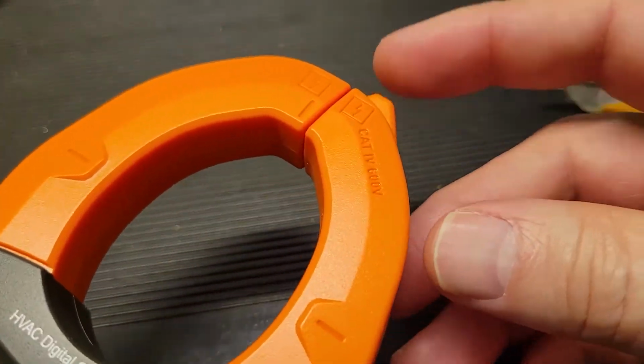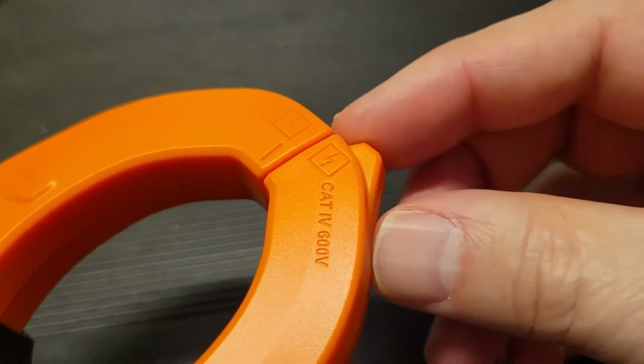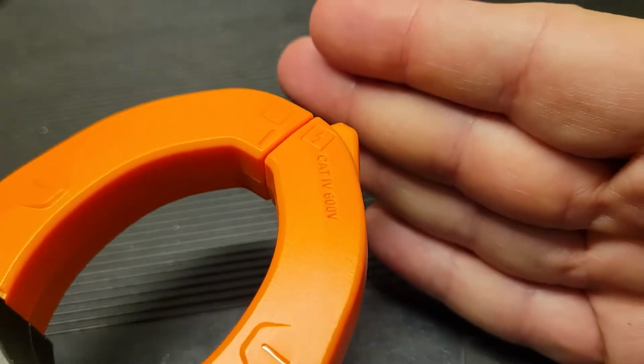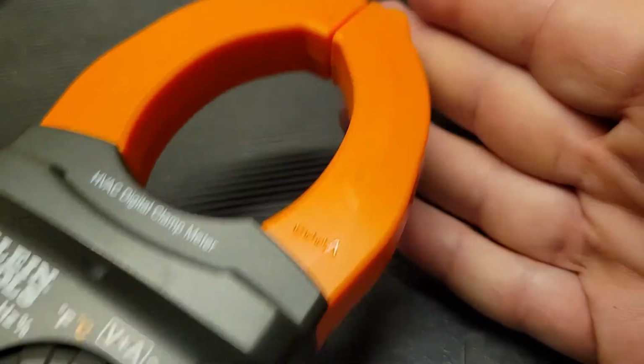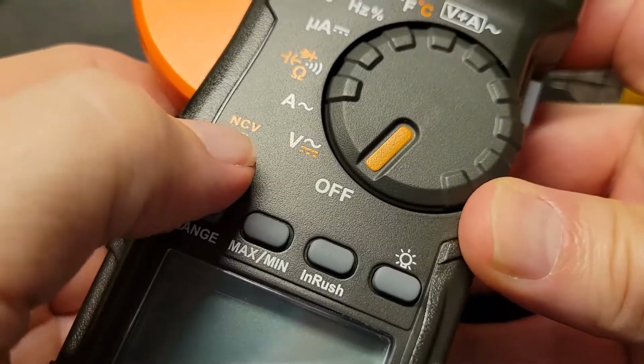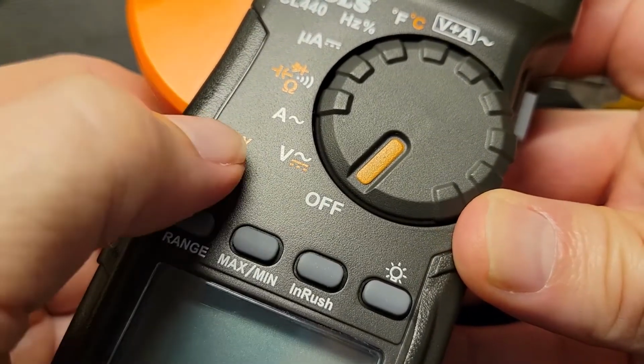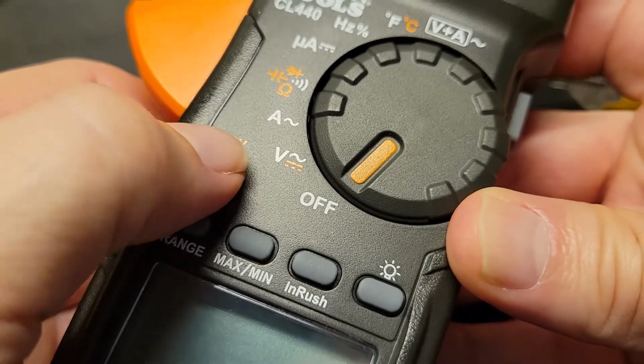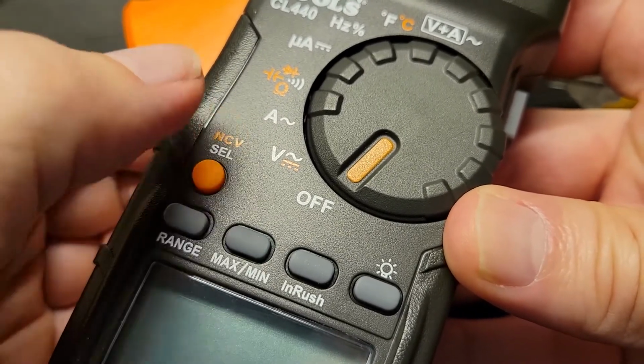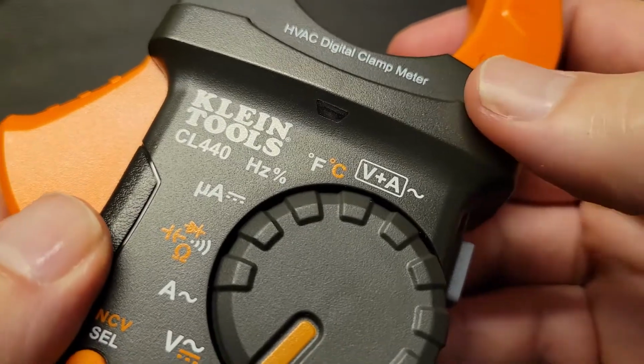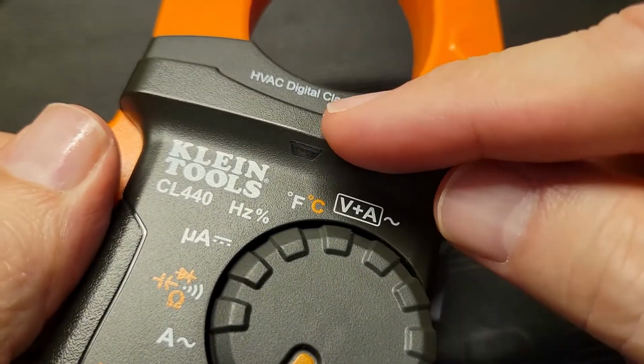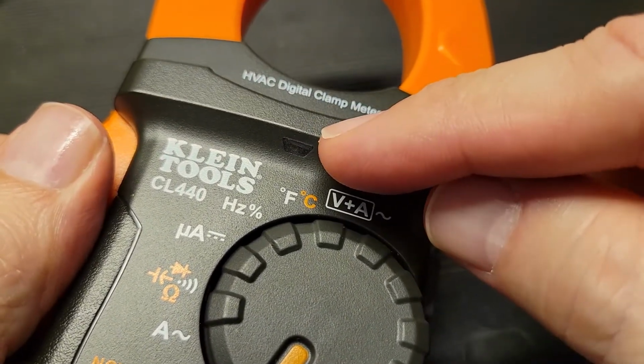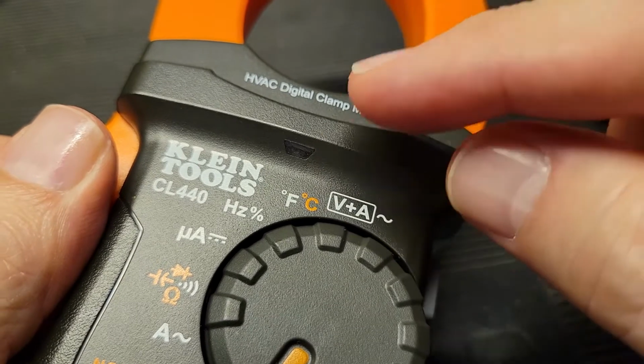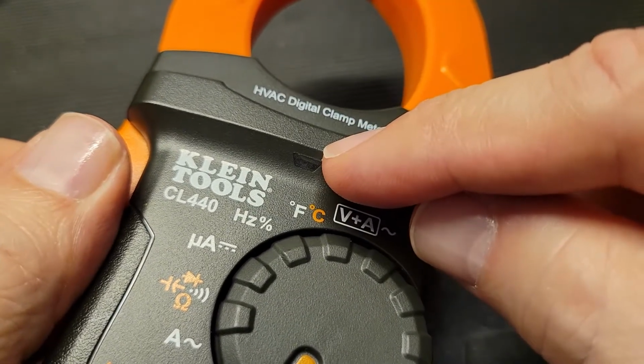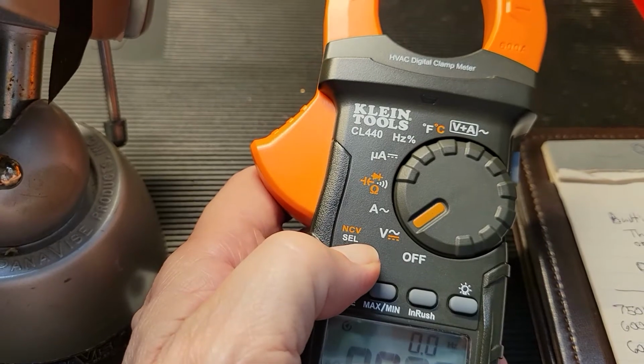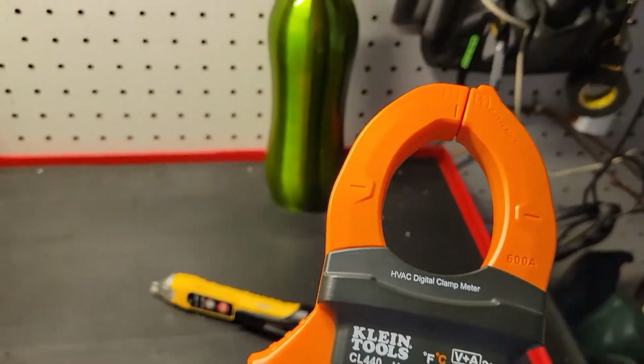Likewise, this portion of the clamp, this little knobby here, if you put this up against an outlet and there's voltage present and you're holding down, this is a function that you literally have to hold the entire time. It's not a toggle on, toggle off kind of thing. That will enable this function to work, and what will happen is you'll get a light and a tone indicating that there is voltage present.